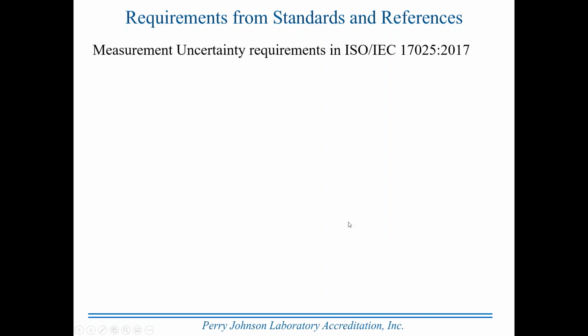Now let's look at the requirements related to measurement uncertainty that are found in the standards and references that we have to work with. Measurement uncertainty requirements in the 17025 standard. Now, when we're talking about the standard today, unless it's a measurement standard, and I'll try to identify those, we'll be referring to the ISO/IEC 17025:2017 standard. The 2005 standard will be totally obsolete as of the 29th of November this year. Everyone, if you're accredited or in the process, needs to be working with 2017, that version of the standard, for accreditation.